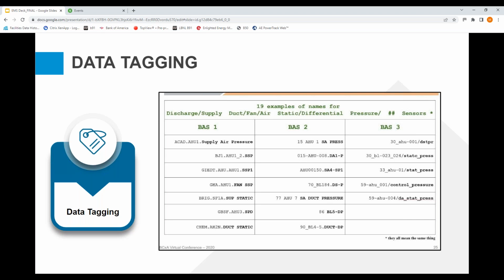Once we do get them talking, the controls contractor is able to bring in all these data points, and they may look similar to what you're looking at on the screen right now. I like to say it looks like a foreign language because it's usually just a bunch of letters and numbers that don't make sense. It doesn't tell me that it's an occupancy sensor versus a photo sensor, and it surely doesn't tell me where it's located - what building, what floor, what room.